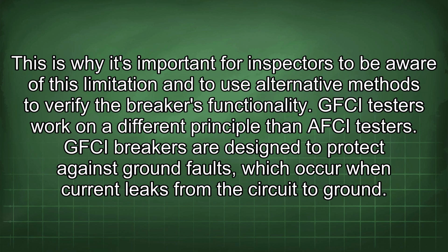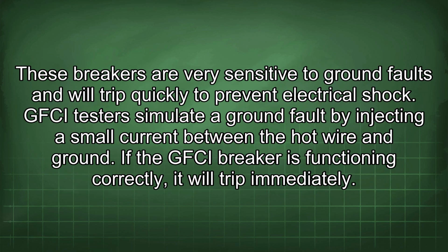GFCI testers work on a different principle than AFCI testers. GFCI breakers are designed to protect against ground faults, which occur when current leaks from the circuit to ground. These breakers are very sensitive to ground faults and will trip quickly to prevent electrical shock. GFCI testers simulate a ground fault by injecting a small current between the hot wire and ground. If the GFCI breaker is functioning correctly, it will trip immediately.